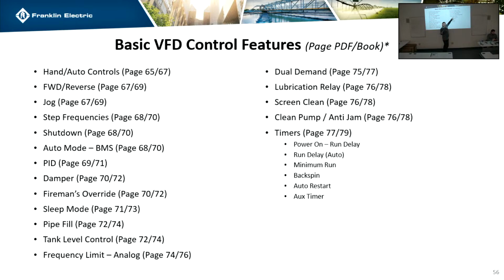All these demo units are set up with it, so you can actually see it work. If you just turn it off and turn it back on, you'll see a power up on delay, and it's set for 10 seconds. So basically, anytime you get a run signal after it's powered on, you can't run it before 10 seconds. And it just says power on delay. It tells you what it's doing.